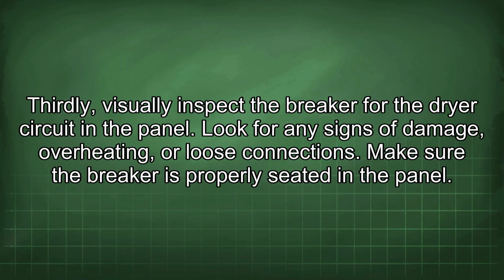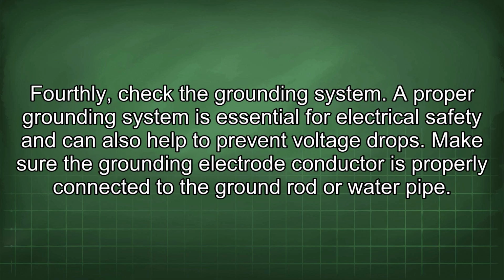Thirdly, visually inspect the breaker for the dryer circuit in the panel. Look for any signs of damage, overheating, or loose connections. Make sure the breaker is properly seated in the panel. Fourthly, check the grounding system. A proper grounding system is essential for electrical safety and can also help to prevent voltage drops.